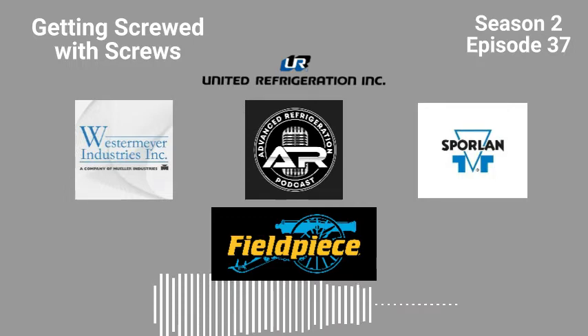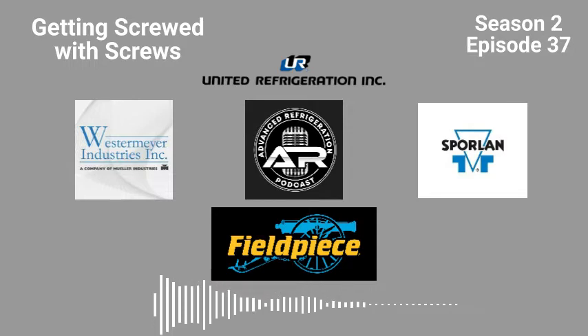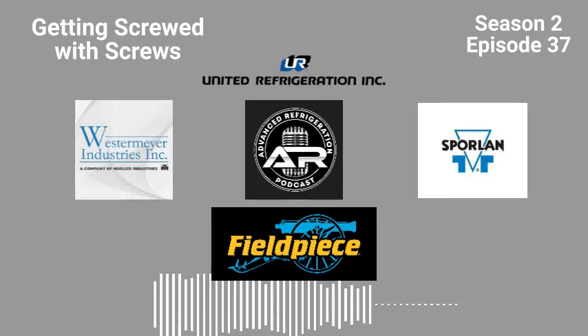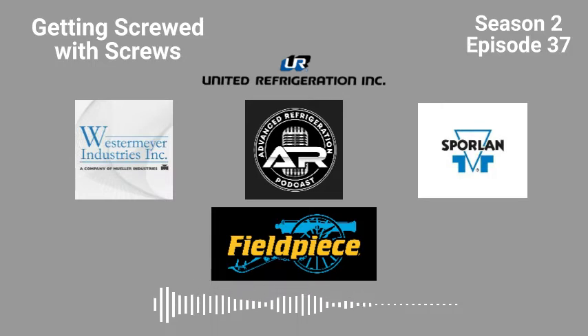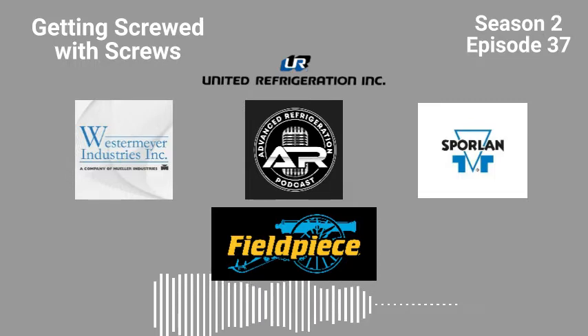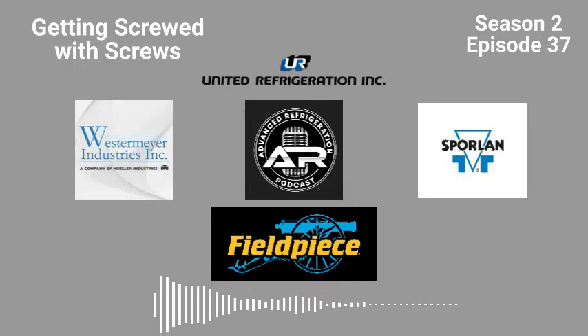Well, yesterday number 3 kept tripping on oil. It tripped on oil like 3 or 4 times. With a million other things going on, I didn't have time to deal with it. So service was supposed to come out, look at it, and dig into it, see if we needed an oil switch or what, because it would time out for like a minute and it would shut off. So I'm like, okay, whatever. I go about my day, and we're starting up this freezer now.